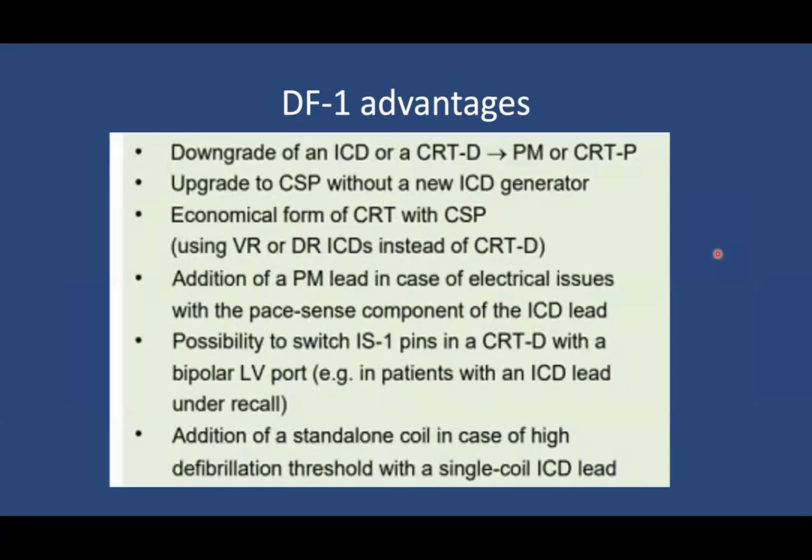But there are advantages in a DF1 device and a DF1 lead. And the devices will need to continue to be made for another 20 or 30 years because many patients have DF1 leads, and there isn't an appetite to create appropriate adapters to convert them into DF4 leads. The first one is patients who have recovered ventricular function and don't need an ICD can have a downgrade because you can plug the IS1 part of the DF1 lead into the CRT LV lead port.